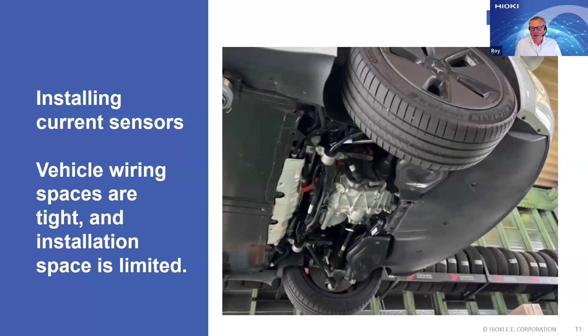We need one from HIOKI. The terminals are special from HIOKI, not BNC. Our current sensors have a dedicated connector, and normally we don't use the BNC connector, which probably isn't on the instrument at all anymore. In the past it was with the 3390, but it's not possible to connect the current sensor with a BNC connector to the PW4001.